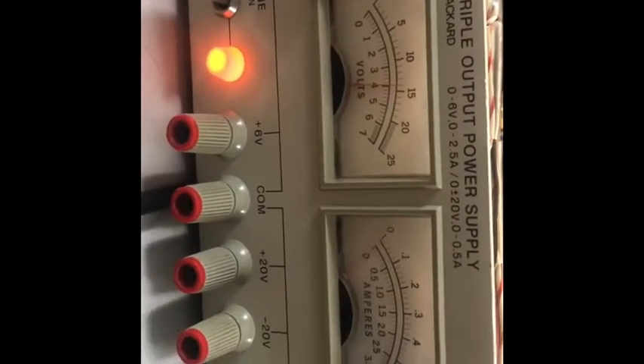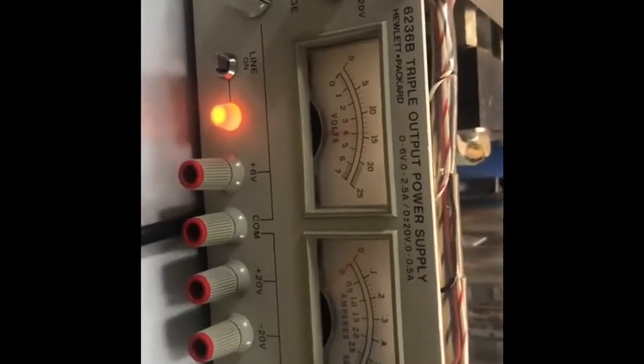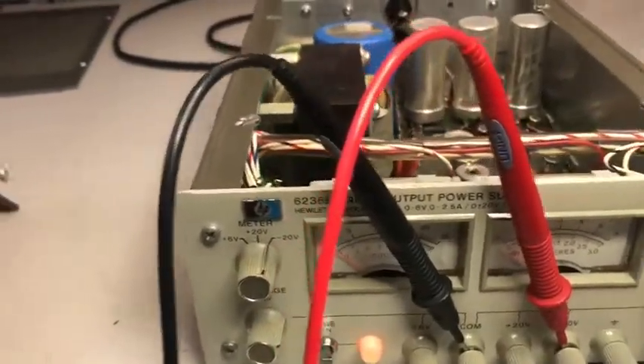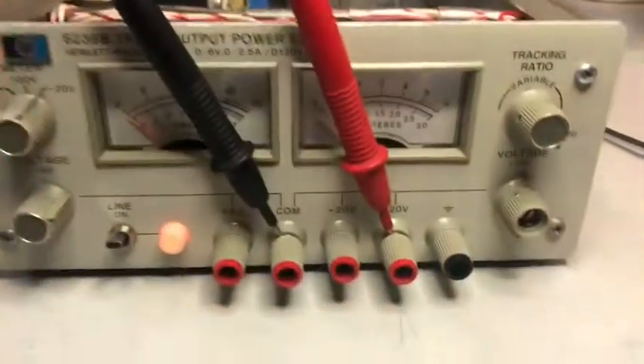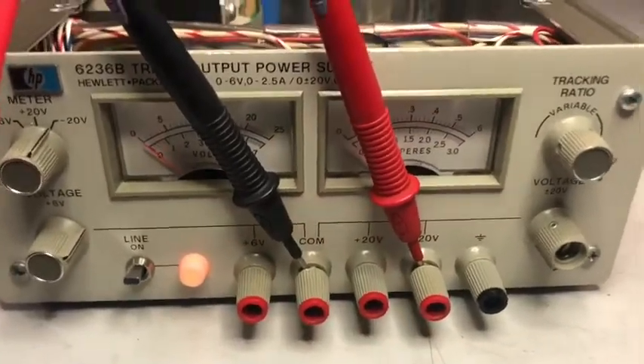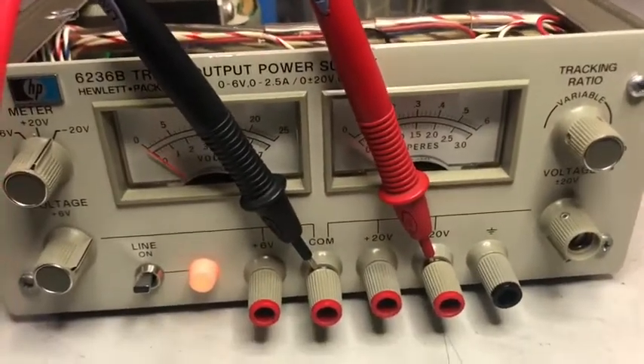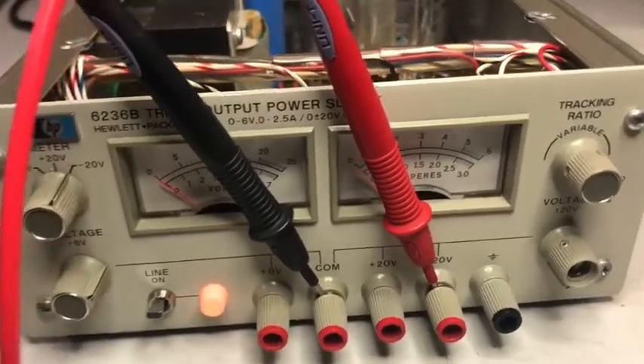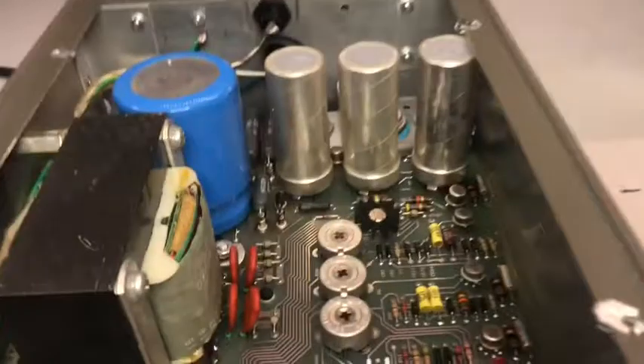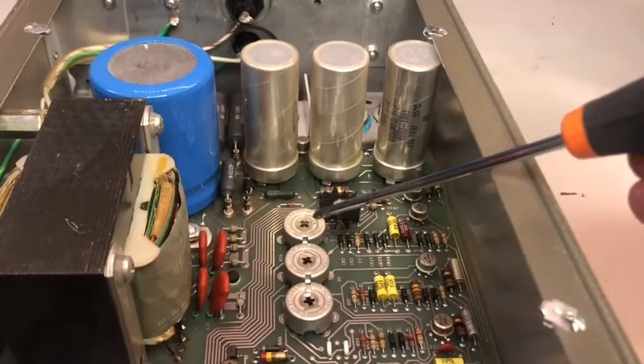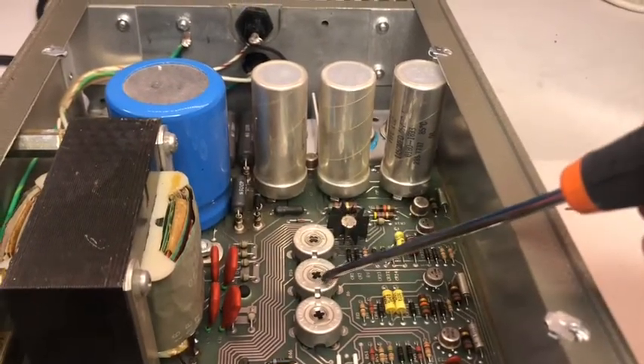So I will do this small modification and the adjustment procedure, then test the unit with some load. Let's go ahead. According to the service manual, the output of minus and plus 20 volt should be regulated at 0.55 amps through the relevant trimmer. This one is for -20 and this one is for +20.